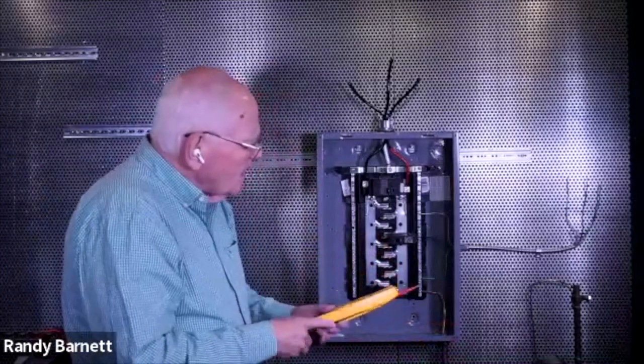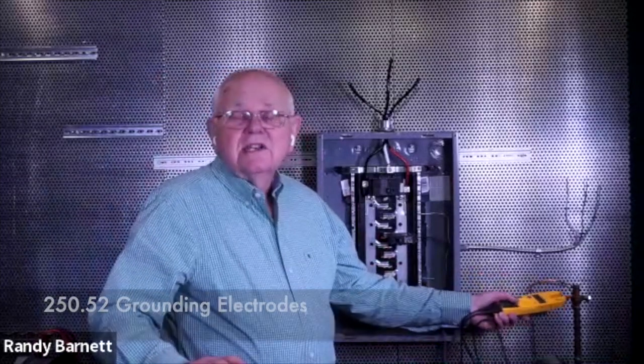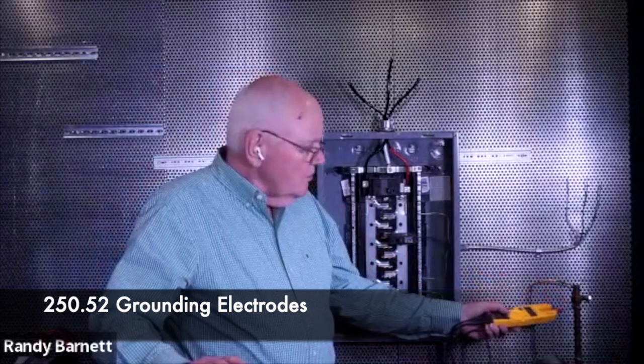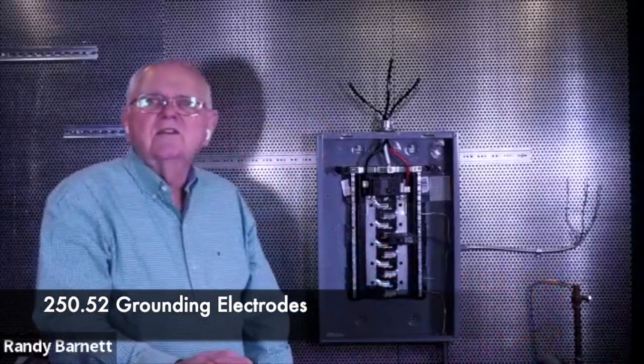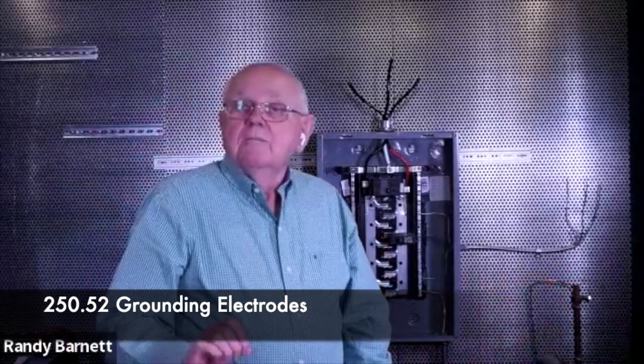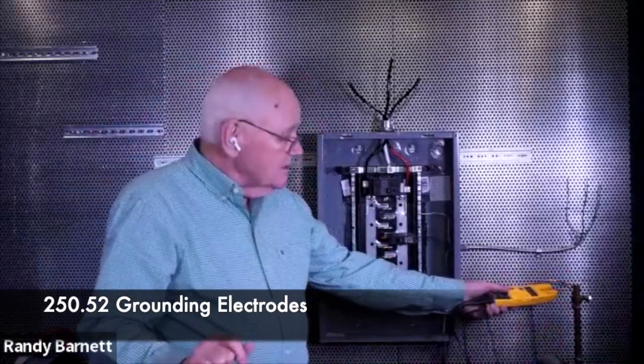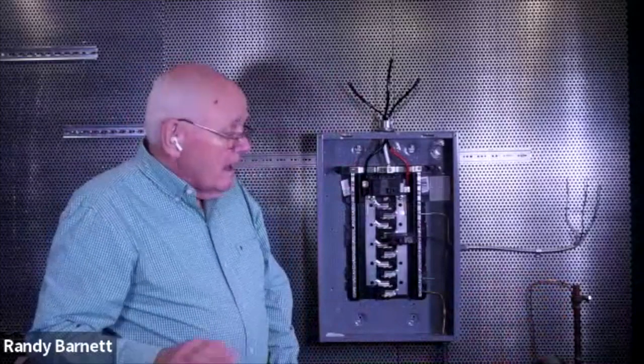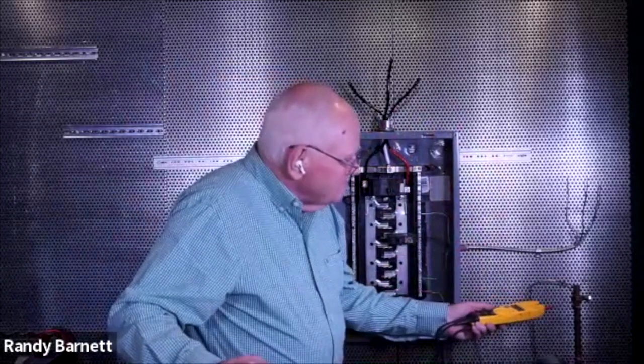So we've got a ground rod over here driven into the earth. I can go to Article 250, Section .52. So 250.52 is going to tell me 8 different items that I can use for my grounding electrode. By definition, back in Article 100, the grounding electrode is the item we put into the ground, into the earth. So there are 8 different types of grounding electrodes that we can have. And I may have more than one. I can have an entire grounding electrode system. That is what we're going to have to install, or talk about anyway, here in a minute. And so 250.52 tells me what I can use.